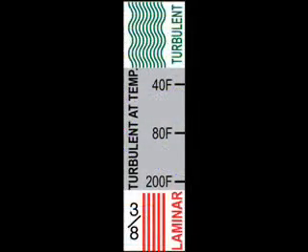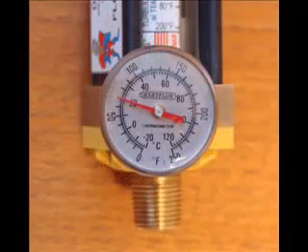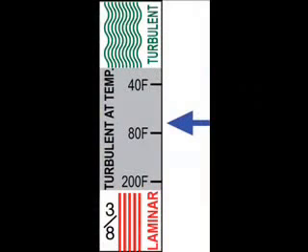We coined the phrase fluid characteristic indication to describe our method. Here's how FCI works. An FCI scale has three zones. The laminar flow zone has parallel red lines, and any flow in this area should be considered laminar. The gray area is a transitional zone, turbulent depending on water temperature. Turbulence is assured in this area by merely adjusting the flow to the temperature marking that matches your water temperature. And finally, there's a turbulent zone with wavy green lines to indicate that any flow in this area will be turbulent. It really is that simple.